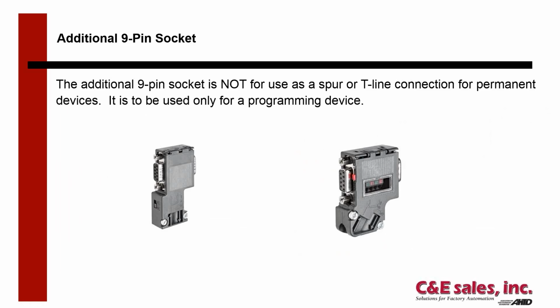All right, but again, it is not for use for connections for permanent devices. If you're listening to the sound of my voice and you've got a variable frequency drive hooked up to the back of this guy, or a remote I/O, or even an HMI, that's not a good idea, and we need to think about how we get out of this situation.